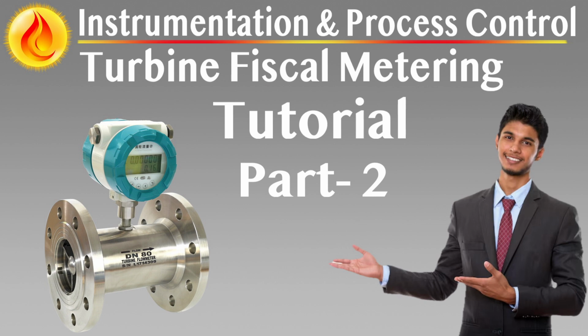Lightning and surge protection. For outdoor installations not protected by structural shielding or lightning conductors, dedicated surge protection measures must be included. This applies to all signal and power lines that extend beyond the skid boundary, particularly those running in parallel with long metallic paths. Surge arresters, shielded cable, and equipotential bonding must be employed to prevent transient damage from lightning or power switching events.